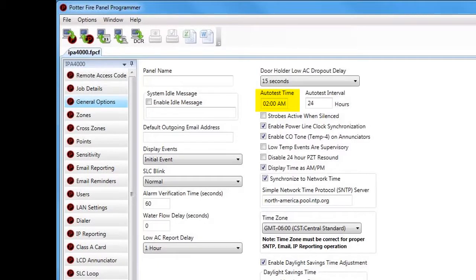Next is Auto Test Time, with a default of 2 AM. This is the time the panel will send the 24-hour test signal to the central station, whether using a dialer or IP, and it is also the time the test email will be sent. Just to the right is Auto Test Interval, where you define the time between test signals sent to the central station. The default is 24 hours, but if a shorter interval is required you can set it anywhere between 1 and 24 hours.